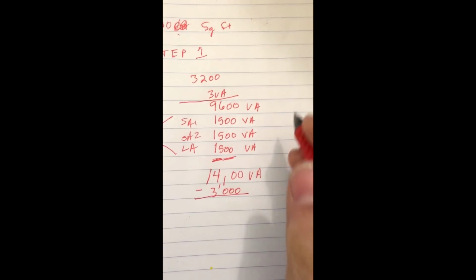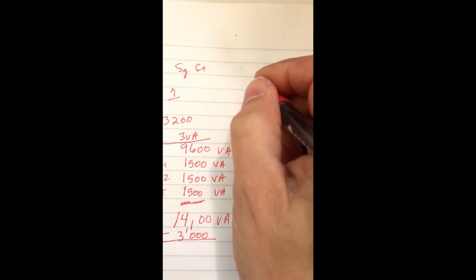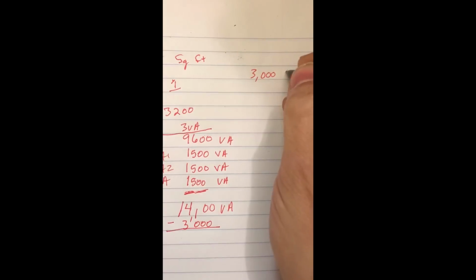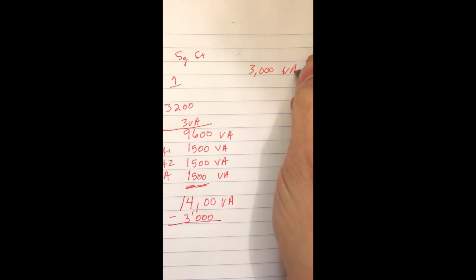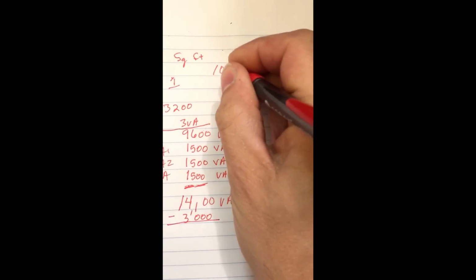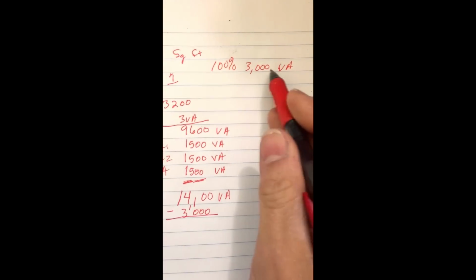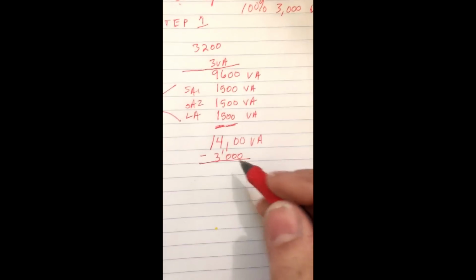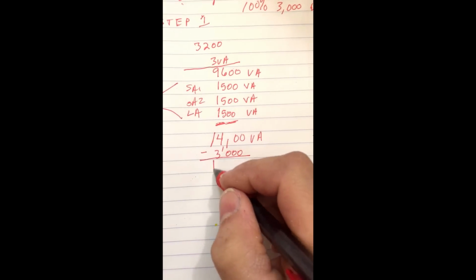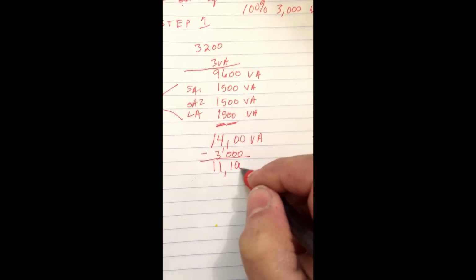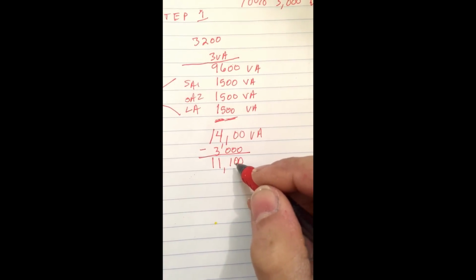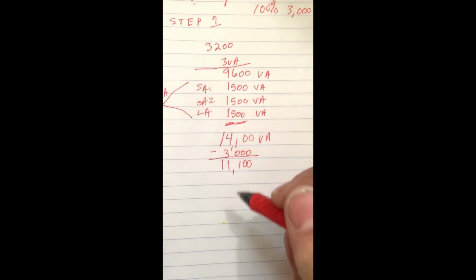I'm taking this 3,000 and putting it up here to the side so I can remember later on that I've got to come back and add it back in. But that 3,000 is 100% of that number. You can't touch that block. It's non-derateable. But the balance down here of what's left over, this 11,100, is the amount that's derateable according to the table in 220.42.